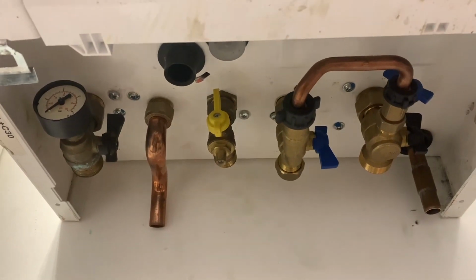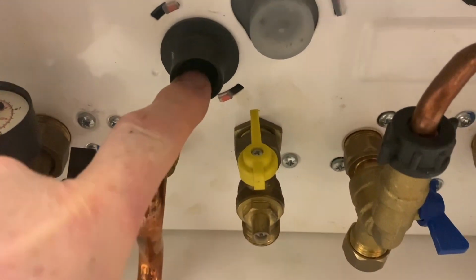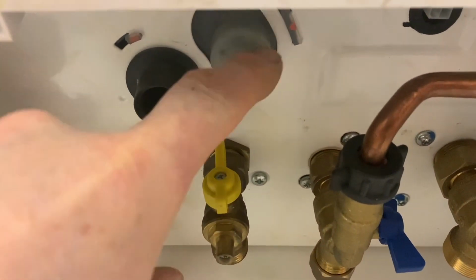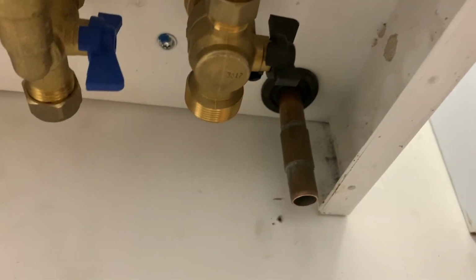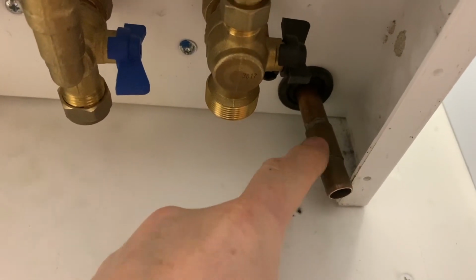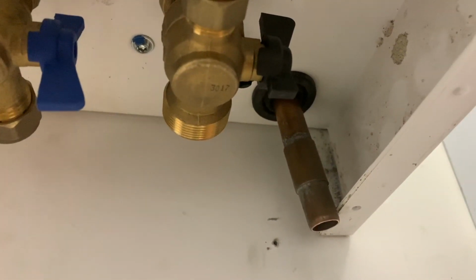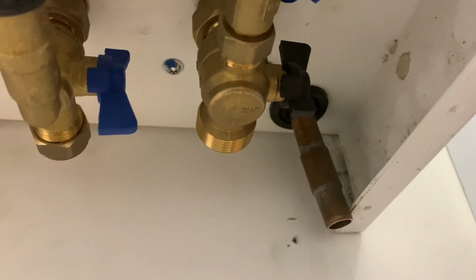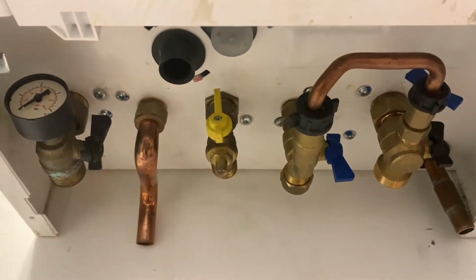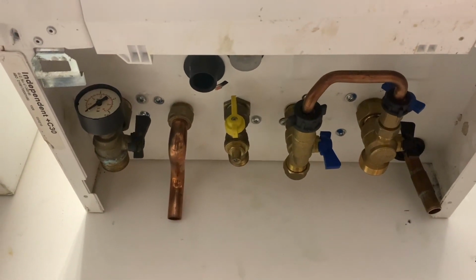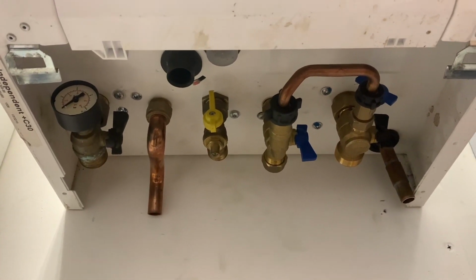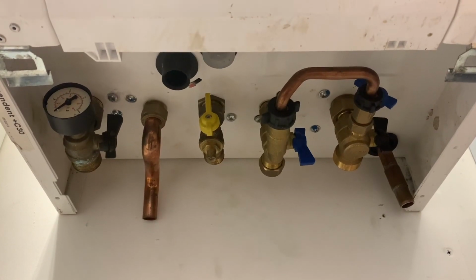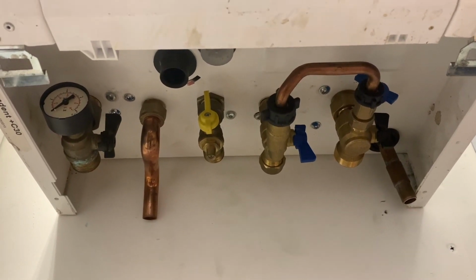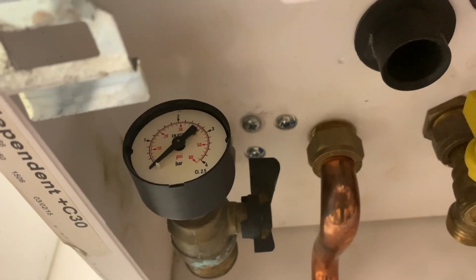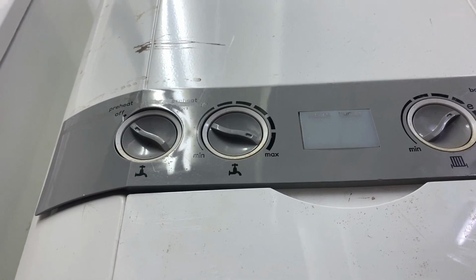The first one I ever fitted of these, it kind of caught me out. So anyway, you can now see this is the condensate, and you can see the trap, but this is the newer version trap, so it doesn't have the nut on the bottom. And the last bit at the back is our blow off, and this here has been soldered, but it should actually be a compression fitting. So Ideal, when these first came out, used to supply this compression fitting. Now you have to do it yourself, so that would need a compression fitting. So that's the look under the Ideal Logic range of boilers, and they're still exactly the same today, except the pressure gauge is now to the left there.